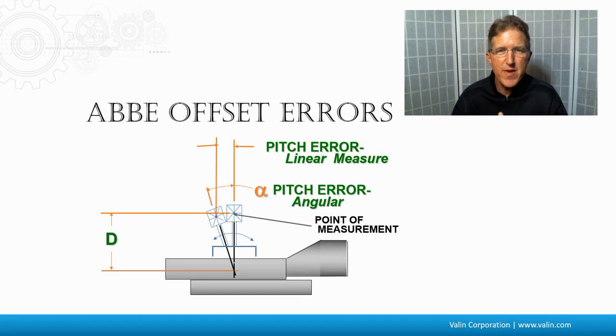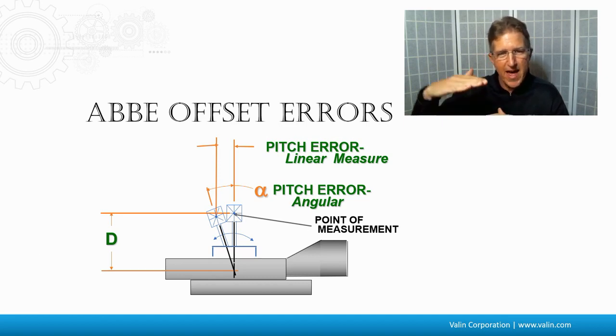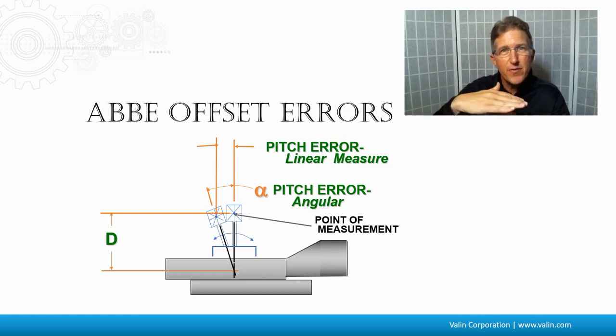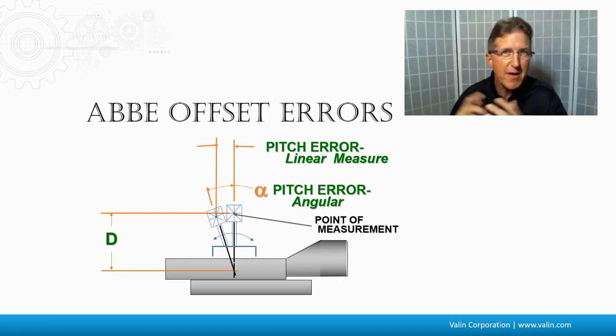As the carriage moves, there may be some Abbe offset errors, which can introduce some angular offset. There's a pitch error and an angular error. So if the carriage actually has some pitch, yaw, and roll as it goes along the movement — because nothing is perfect — that point an inch or two above the carriage is going to have a little bit of Abbe offset error.